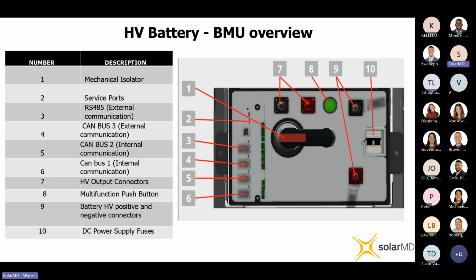Since I'm using the word module so much, that reminds me that the design is inherently modular. What does that mean to me as the installer? Well, when you look at other brands and their solutions in the marketplace, they produce nice enough high voltage batteries. However, to meet your energy storage requirements, if you want an 80 kilowatt hour battery or a 200 kilowatt hour battery, they produce one large single battery. That becomes a logistical nightmare to get this battery to and from site. Moreover, if you're facing problems with the battery on site, you can't easily repair it on site, and you can't exactly return the faulty component.